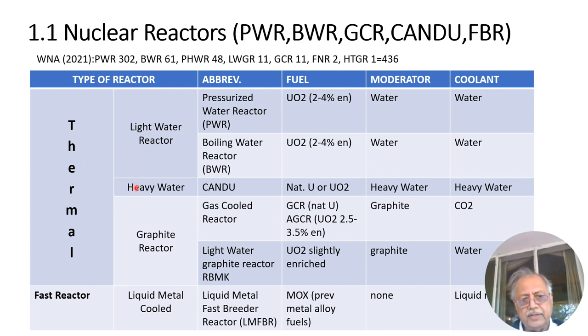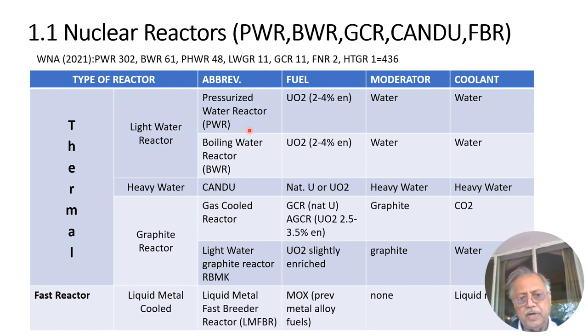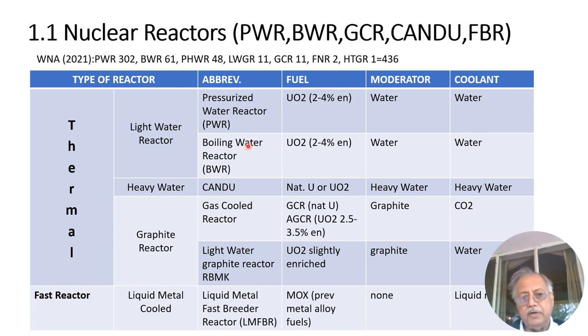In the thermal group, we have light water reactors, heavy water reactors, and graphite reactors. The two main light water reactors are the PWR and the boiling water reactor. Both use uranium dioxide fuel enriched to 2–4%, moderated and cooled by light water. The term pressurized in PWR stands for high pressure — 2250 psi — which allows water to operate up to 285°C without boiling, giving good thermal efficiency. Boiling water reactors allow boiling and operate at lower pressure.